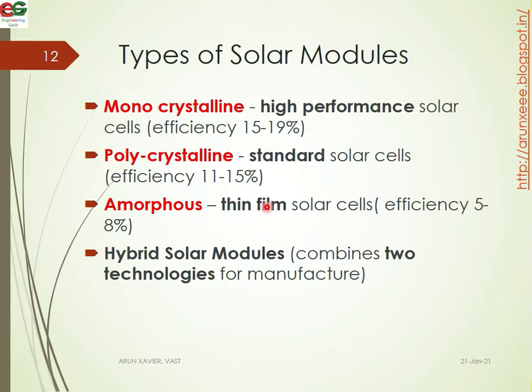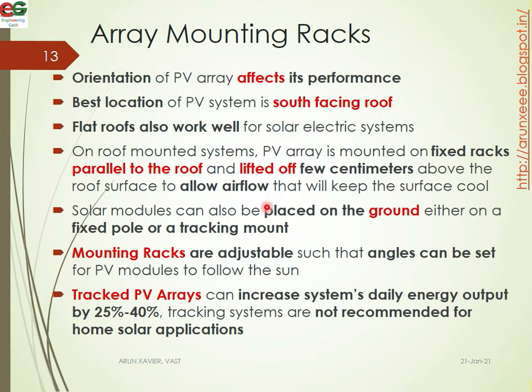Hybrid solar modules combine two technologies. The next component is the array mounting racks. The orientation of the PV array affects its performance. The best location for a PV system is a south-facing roof. Flat roofs also work well for solar electrical systems. On a roof mount system, the PV array is mounted on a fixed rack parallel to the roof, lifted a few centimeters above the roof surface to allow air flow and keep the modules cool.